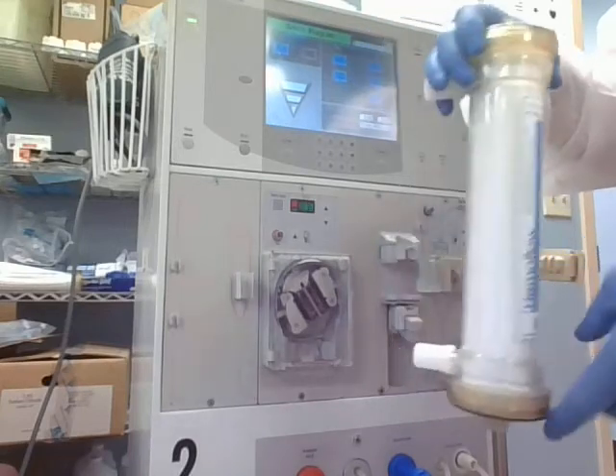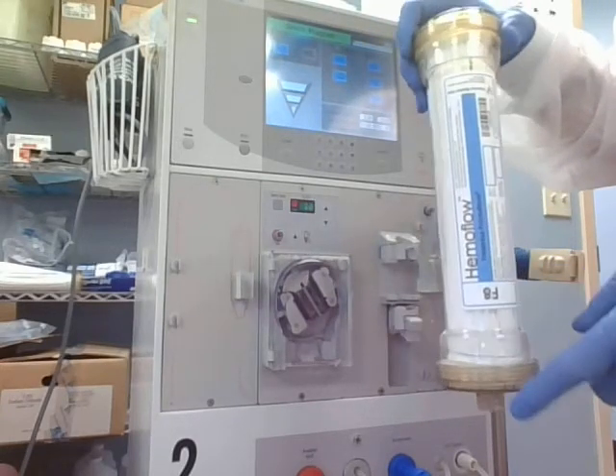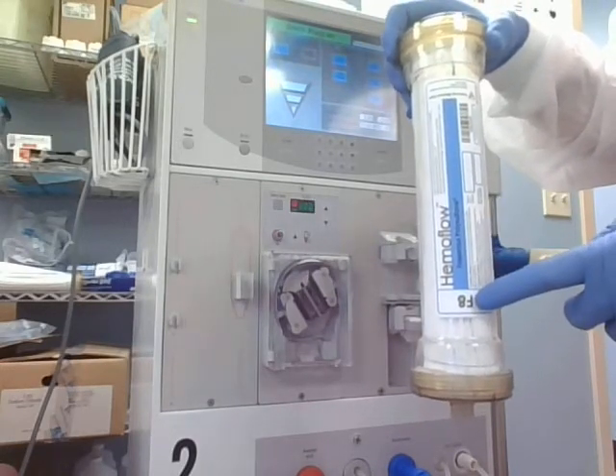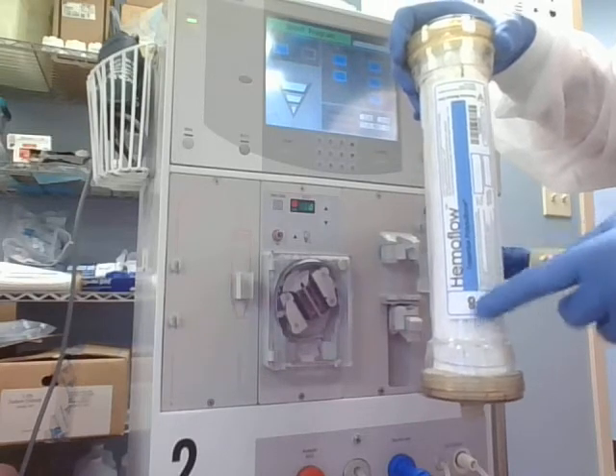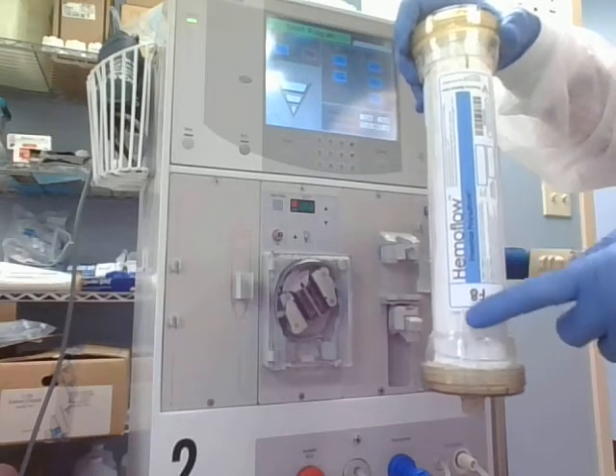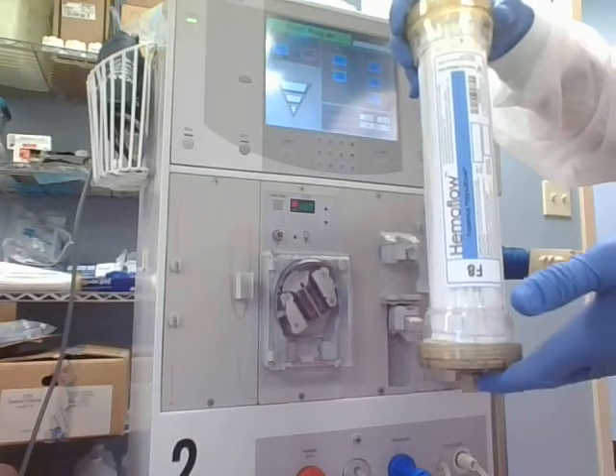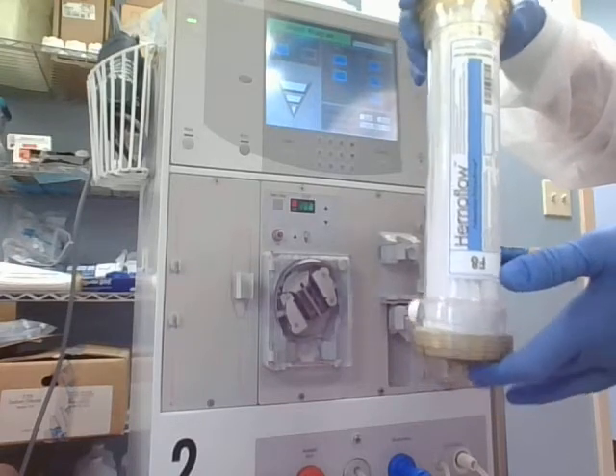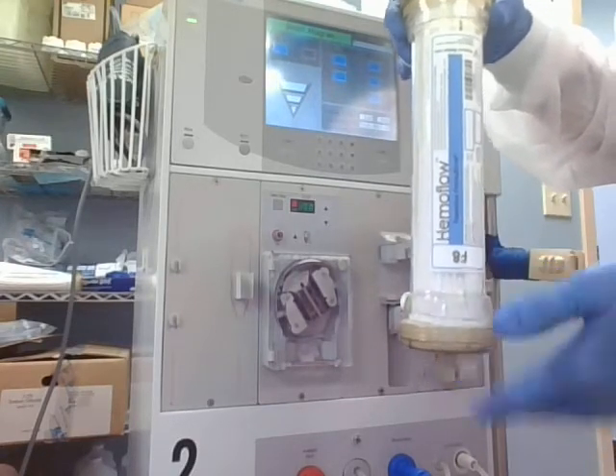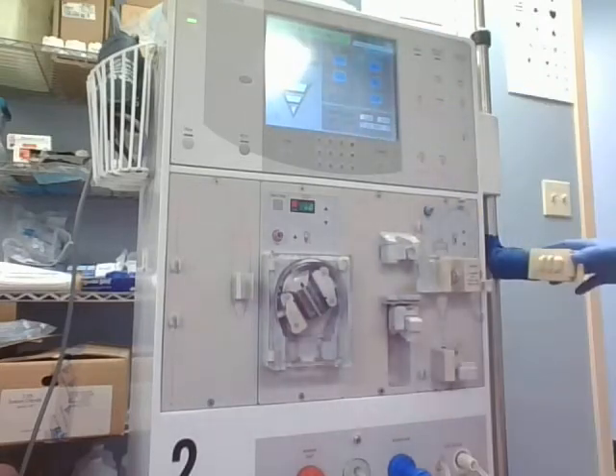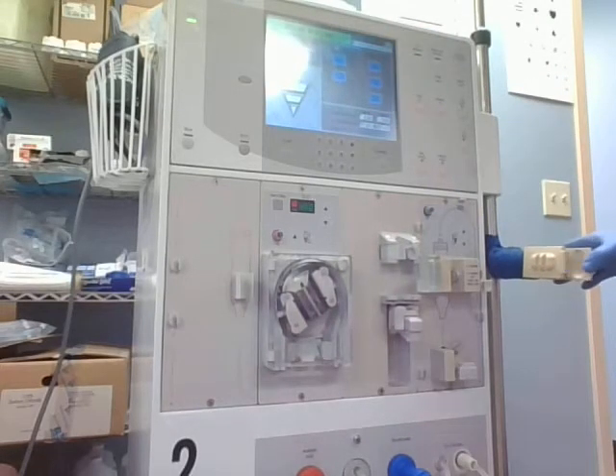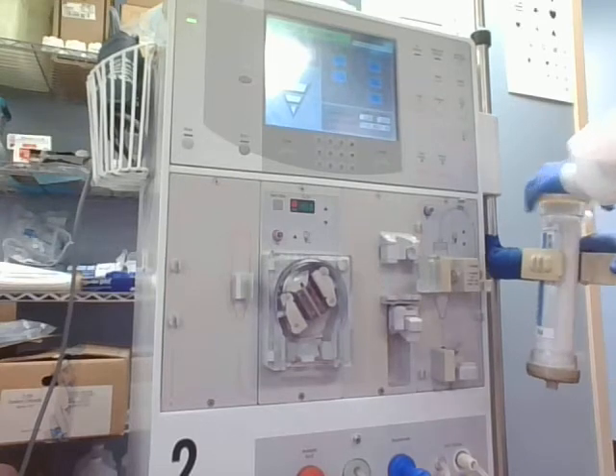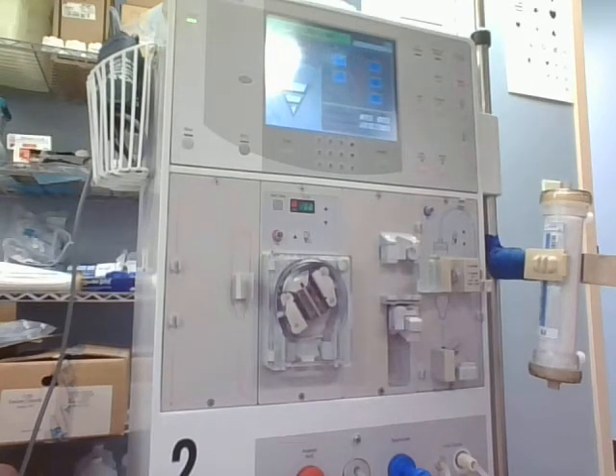Now, how do I know what's right side up and what's right side down? Fortunately, they label the dialyzers. Where this number is going to be considered the top of the dialyzer. So I want to seat it to begin with upside down. I want the top on the bottom. In order to seat my dialyzer, it's very simple. I have this little dialyzer holder over here. It has a clamp on it. So you take your thumb and pull that clamp back and seat your dialyzer, and it should hold that steady for you.